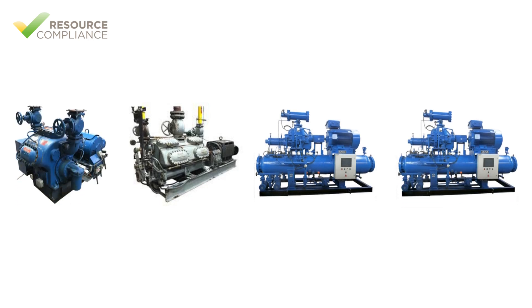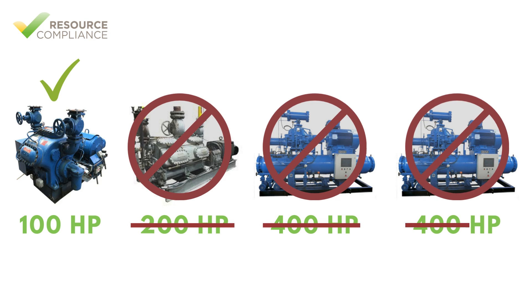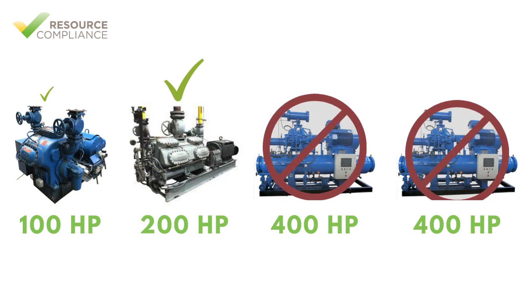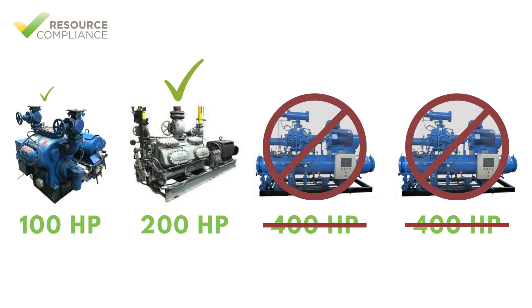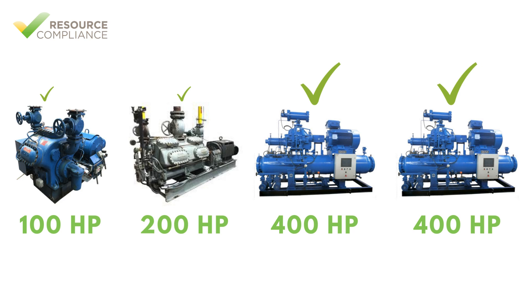For example, let's consider a hypothetical system with a 100 horsepower, 200 horsepower, and two 400 horsepower compressors. When the system load is minimal, the 100 horsepower compressor will be the primary machine. When the load exceeds the 100 horsepower compressor capacity, the 200 horsepower compressor will take over and the 100 will meet any excess capacity needs. For larger loads, one or both of the 400 horsepower compressors may be required. The most efficient operation will have as many compressors as possible operating fully loaded and the 100 horsepower compressor trimming the remaining load. The compressor performing that function is often referred to as the trim compressor.